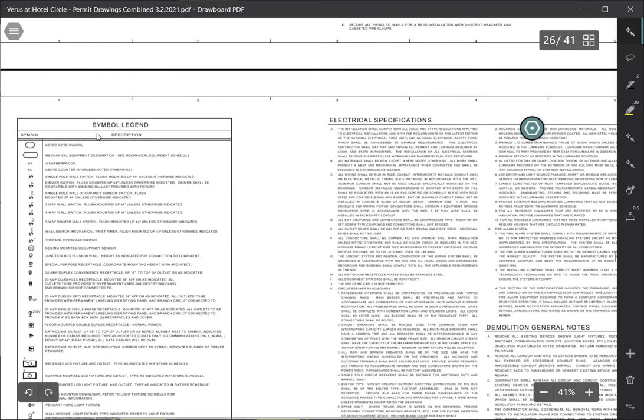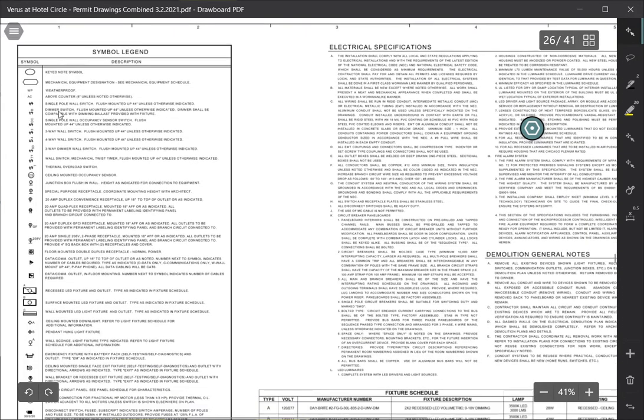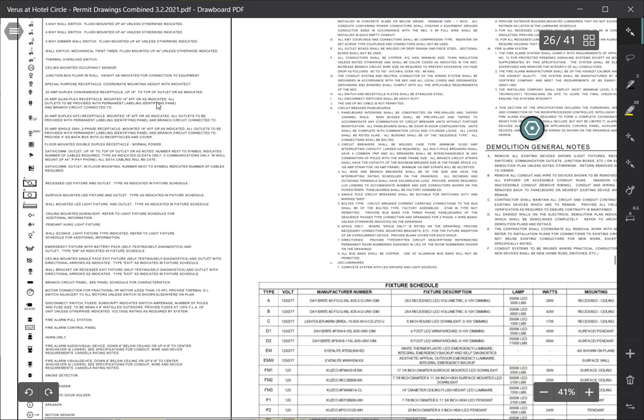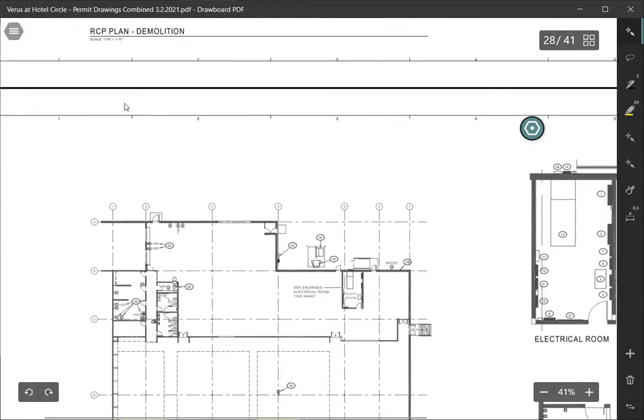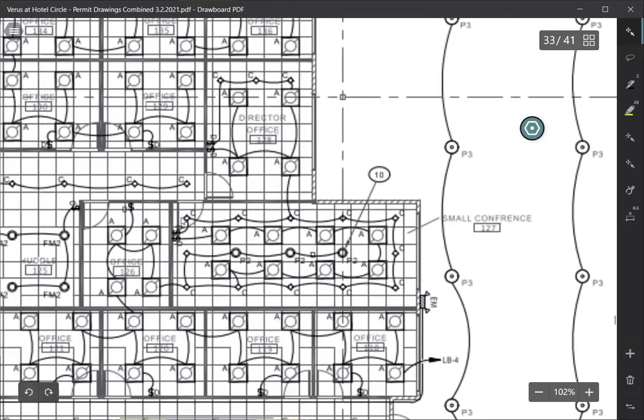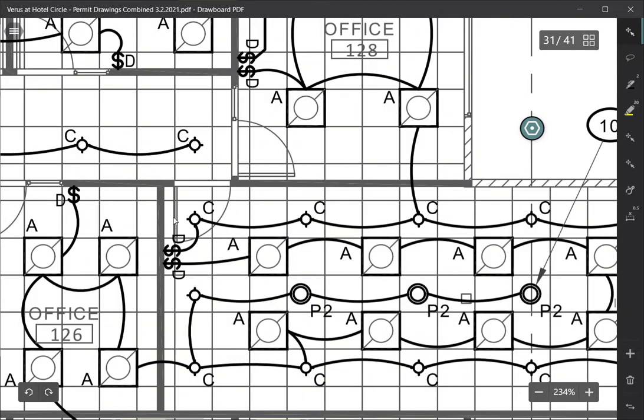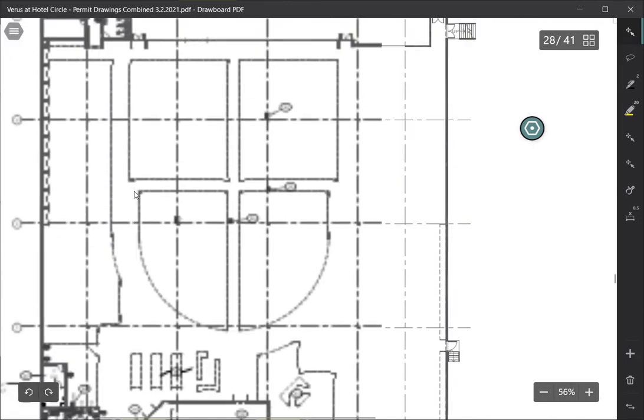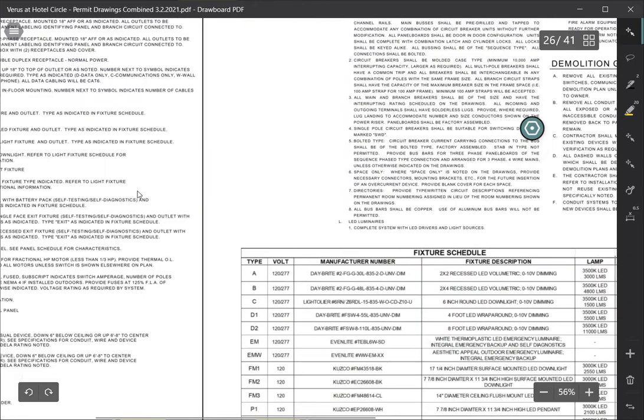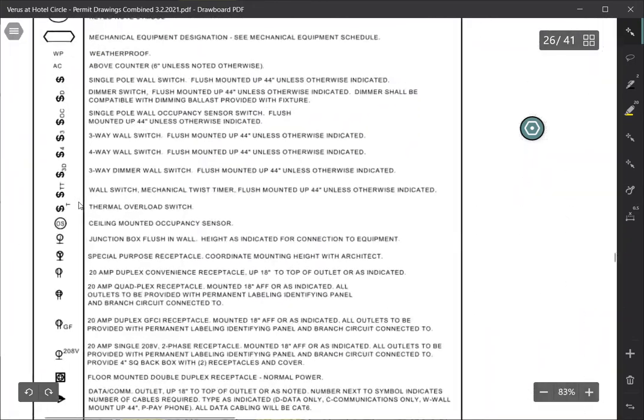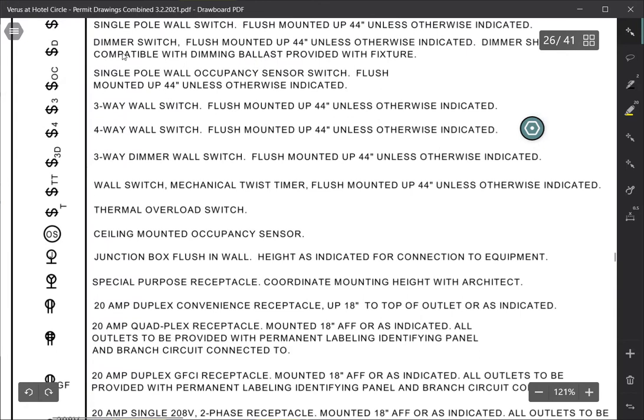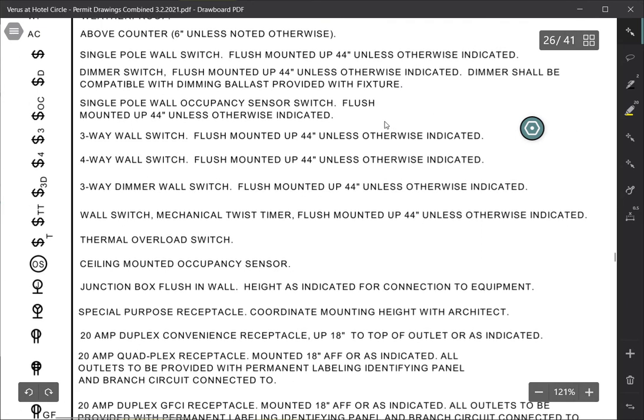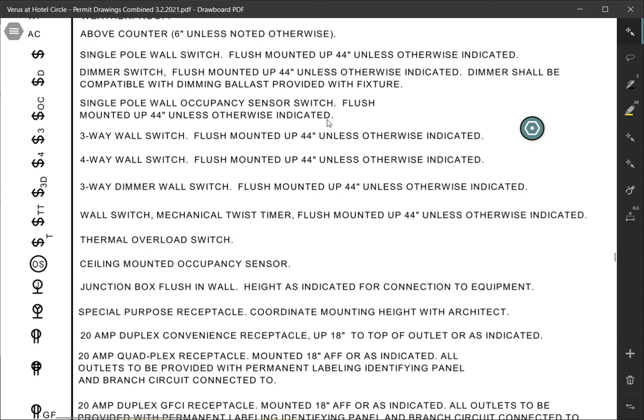So symbol legend, let's see, this is going to tell you exactly what it is on this. So let's just do a quick example right here. So these little guys are switches with a D, and if we go back up to see what that is, just for this particular example, we are looking at a switch with a D, which is a dimmer switch that's flush mounted up to 44 inches unless otherwise indicated. So, what that is saying in a nutshell is that you need to get a dimmer switch, it needs to be flush mounted up to 44 inches, and it's going to stay up to 44 inches unless it is specifically noted on the plans that it needs to be a different height. So, that is what that means in a nutshell.